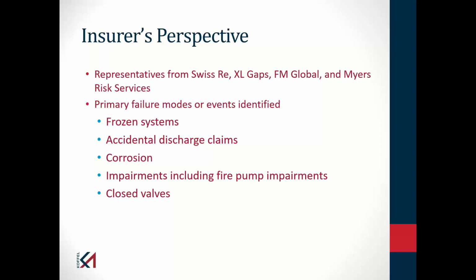So a number of years ago, I was sitting in my office in Columbia, Maryland, and an attorney called me up and said, I have a fire investigator in this warehouse fire that occurred last night in this fully sprinkled warehouse on the south side of Baltimore. And he said, the investigator thinks that the sprinkler valve is closed. I need you to go out and take a look at it, which I did. And yes, the valve was closed. And I came back and I called the attorney and I said, yes, the valve is closed. And my preliminary research indicates that Baltimore City Fire Department did not close that valve during their suppression activity. So most of the time, if it's a fire, the fire department's not going to do that.